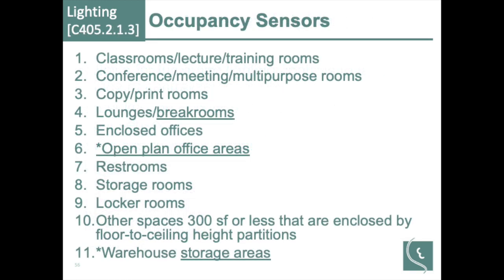Occupancy sensors are now required in more spaces. A big change. Open office areas are now required to have occupancy sensors. Warehouse storage areas also are added into that over the 2015 code. And it should be in each fixture? Occupancy control, it's a set area, I think 600 square feet for open office plan. It has to be under a sensor's control. It doesn't have to be per fixture, but there has to be some control for space.